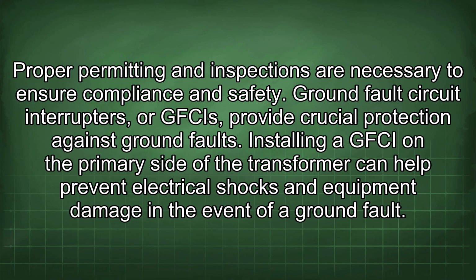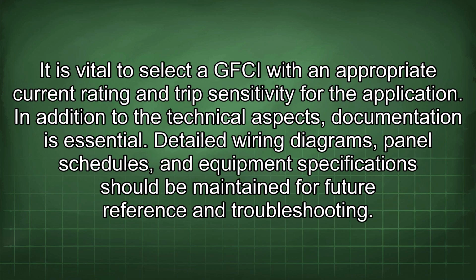Ground fault circuit interrupters, or GFCIs, provide crucial protection against ground faults. Installing a GFCI on the primary side of the transformer can help prevent electrical shocks and equipment damage in the event of a ground fault. It is vital to select a GFCI with an appropriate current rating and trip sensitivity for the application.